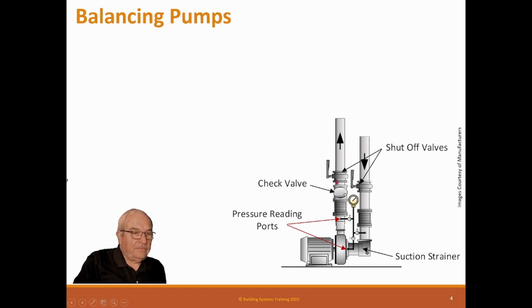Now, I'll talk about my pet peeve right away so we don't have to get into it later: you never, ever need a balance valve on a pump. It's ridiculous. It's ridiculous to think you need a balance valve on a pump. Remember, a pump is basically a metering device, but we also have balance valves downstream.